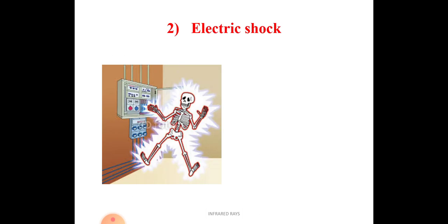Now, many times if the patient is over smart and touches any wire, there are chances that current will enter his body, okay, and he will become part of the circuit. So he will get an electric shock. So what is electric shock? It is nothing but painful stimulation of sensory and motor nerves. Clear? So it is advisable that you instruct the patient not to touch any part of the machine, and even we are not supposed to touch any switch or other electronic equipment with wet hands.